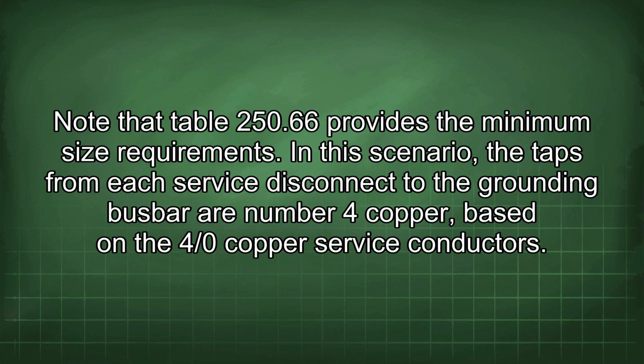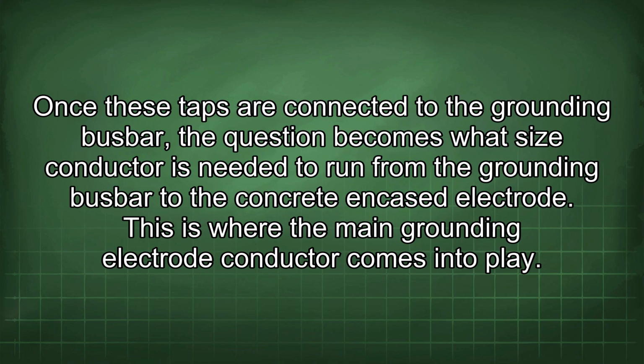In this scenario, the taps from each service disconnect to the grounding busbar are number 4 copper, based on the 4/0 copper service conductors. Once these taps are connected to the grounding busbar, the question becomes what size conductor is needed to run from the grounding busbar to the concrete encased electrode. This is where the main grounding electrode conductor comes into play.